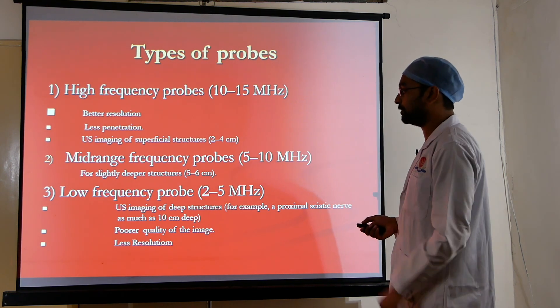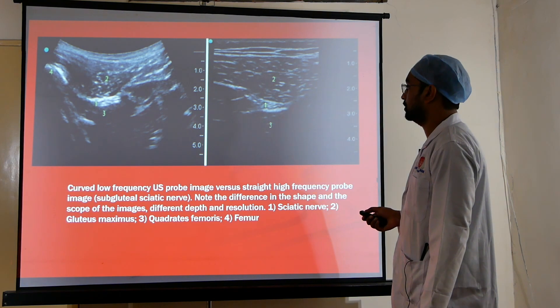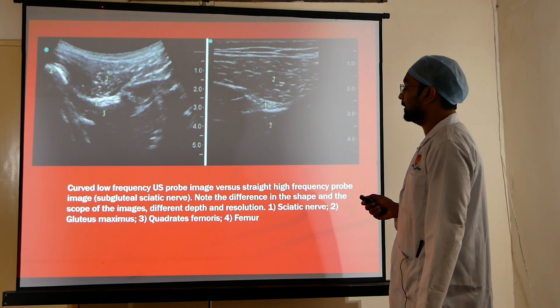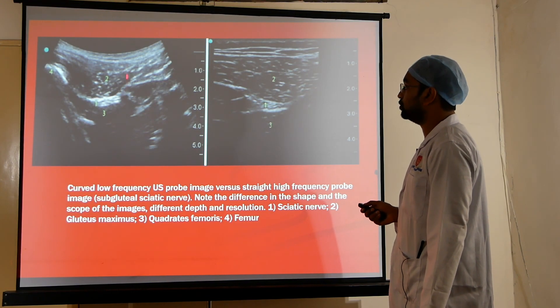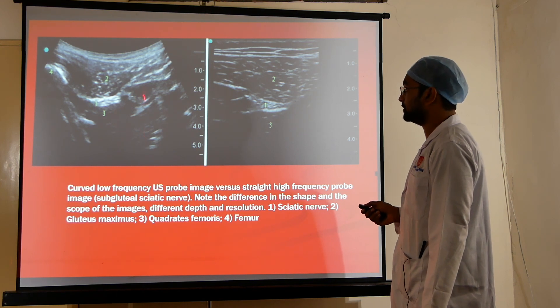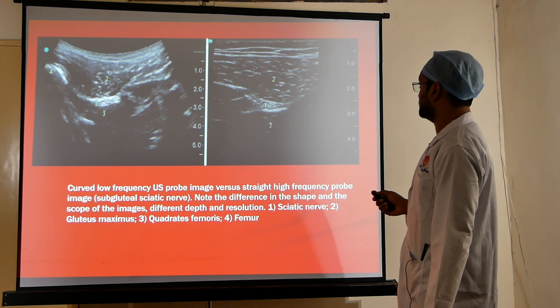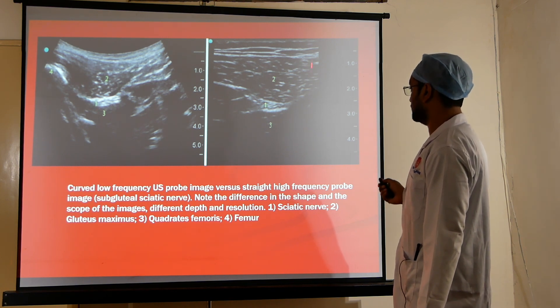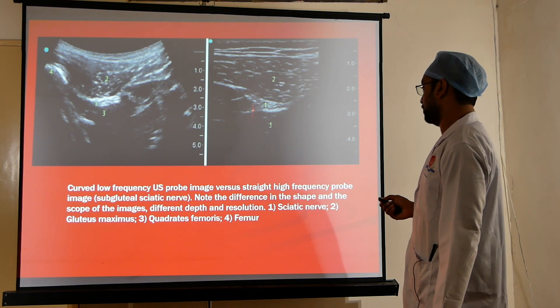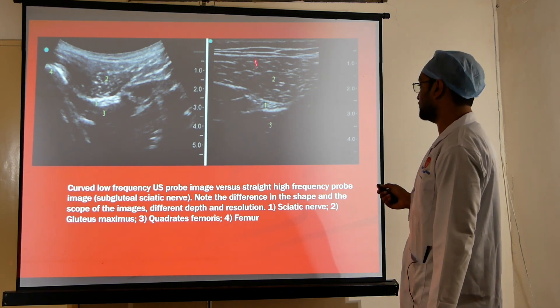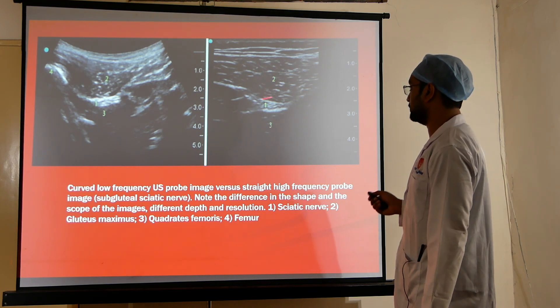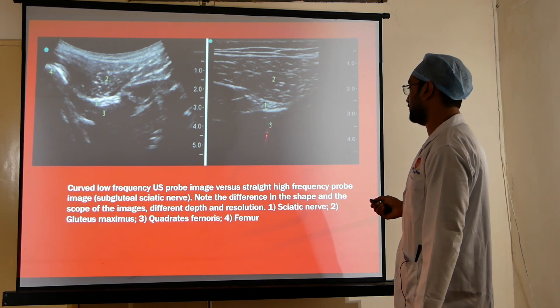Two images generated by different probes: the curvilinear probe, being a lower frequency probe, shows higher depth but less resolution, and produces a curvilinear-shaped image. The linear probe shows the image in a linear cross section with a rectangular shape. We can notice the difference in both the shape and the scope of the images.